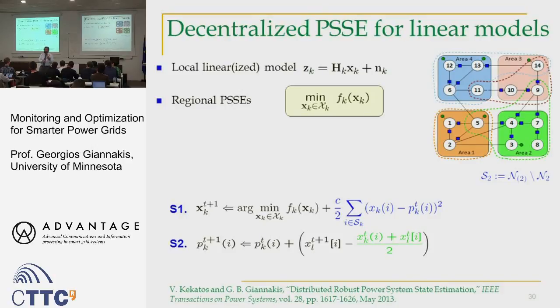It samples 1,000 times faster than the current system. So instead of having one measurement every 4 seconds, that's the current meters, right now we have one almost every millisecond. And you can get the phases also, because you have the timing. They are time synchronized measurements. Okay? So you know how the phase of the sinusoid evolves. But they are expensive, the PMUs.